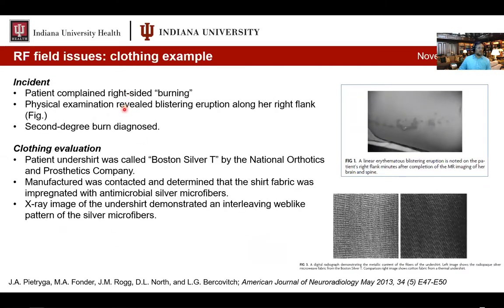During the scan, the patient began to complain of right side burning. You can read more about this in the referenced article. This is an example of the erythema found immediately after the scan. The patient had a blistering eruption along her right flank, a second-degree burn. This was a very serious incident, allowed to develop somewhat because the patient was partially sedated. It occurred strictly because she was wearing clothing with silver fibers in it, later confirmed with a digital radiograph identifying the fibers. This is why we no longer allow people to wear their own clothing. Recent research has shown that 5 to 10% of clothing with these fibers is not labeled as containing them, so you cannot trust the labeling or the manufacturer.